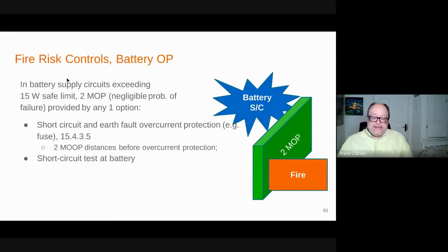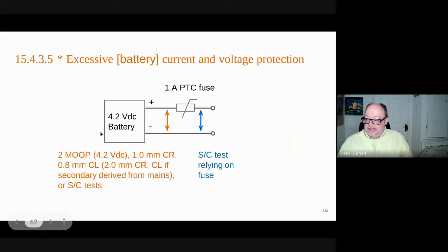With batteries, a similar situation. We've got some joules, and so we should have some fusing. So we're allowed to have a distance of 2 means of operator protection for the voltage. And if we meet that distance, we don't need a fuse. And once we have a fuse, we don't have a distance requirement. We can accept the possibility of a short. And so this is to show that there won't be a short, if you get me. And you'll find that in the 15.4.3.5 battery stuff.